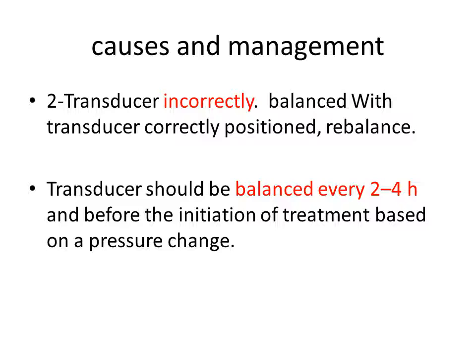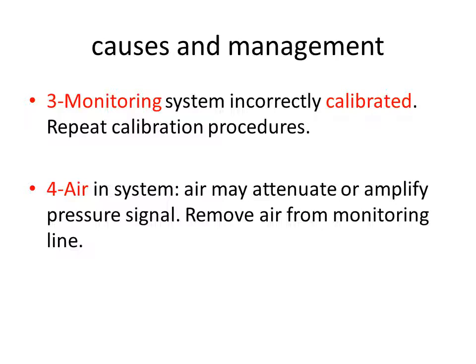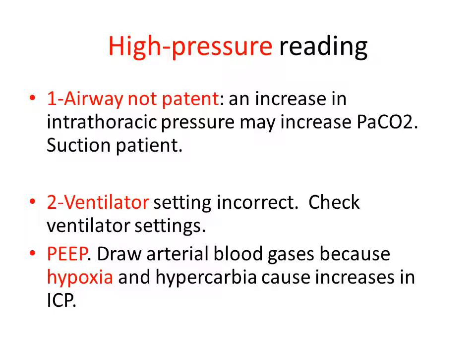And this should be rebalanced every 2 to 4 hours. Monitoring system incorrectly calibrated. Air in system. Air may attenuate or amplify the pressure signals, leading to a false high reading. High pressure reading. This is an actual high pressure reading.